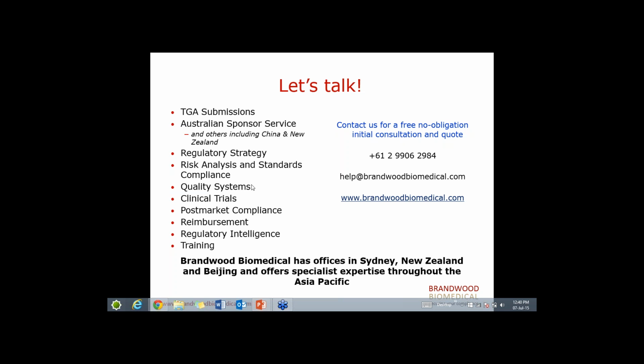If you go through TGA, you have to go through two departments: conformity assessment, and once you've got that, devices. But if you've got an EC certificate, you can go straight into your device application. So it is much more fast track, but in saying that, it could take from a few weeks to a few months, depending on the resources. Also, if the application is selected for an audit, there are additional questions asked by TGA, and that can add time. But compared to TGA conformity assessment, it is a much quicker process.